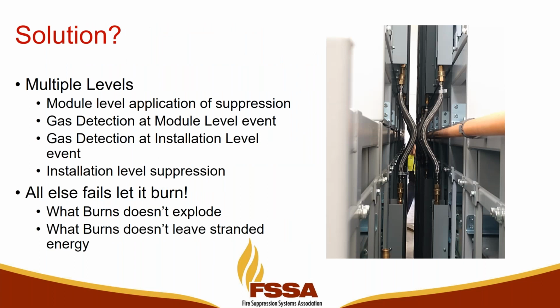So what are the solutions? I mentioned this earlier, multiple levels. Protect the module, look for gas detection at the module level, gas detection at the installation level, then some type of suppression at a building or container level, whatever that may be. Then, if it's just pumping water in, make a dry hose standpipe and let them hook up and fill the thing up as quickly as possible.